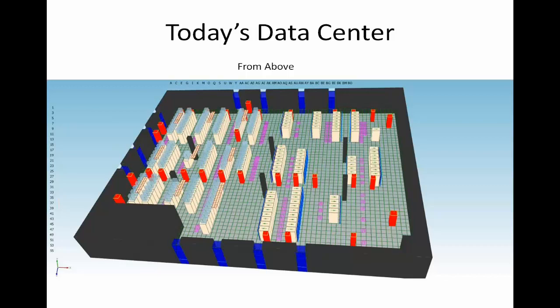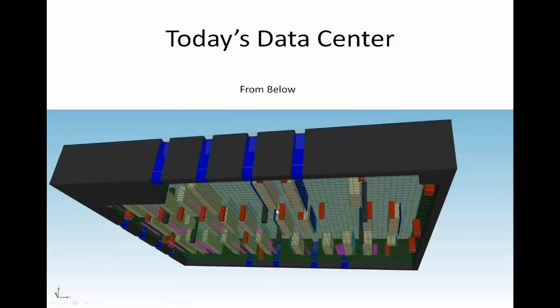In this design, we have rear-door heat exchangers — seen here in blue. We're also using CRAC units along the side because the way this worked is that it pulled air from that third floor plenum down the walls, and the supply was delivered through the floor. We represented that with inlets and outlets — the outlets are at the top coming in through the ceiling plenum, and the supplies are down below. Here's a shot of the underfloor showing the supply ducts coming into the subfloor from the side — there are 12 of them.